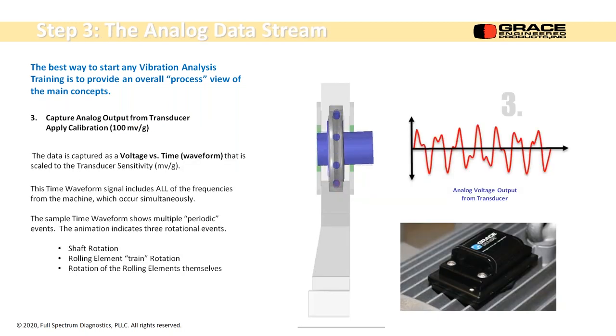I have a little animation of a bearing on a shaft. It looks like the bearing's cocked, and in fact, the inner race of the bearing is cocked, so it's kind of pitching the shaft every revolution. But what's important here, we're going to capture an analog output from the transducer, and it has all the different wiggles, all the vibration of everything that transducer sees is presented here. I'm going to tell you what those three wiggles are. You can't see them right now, but you will in a minute.